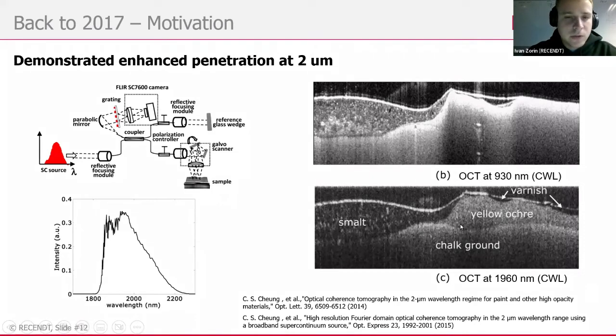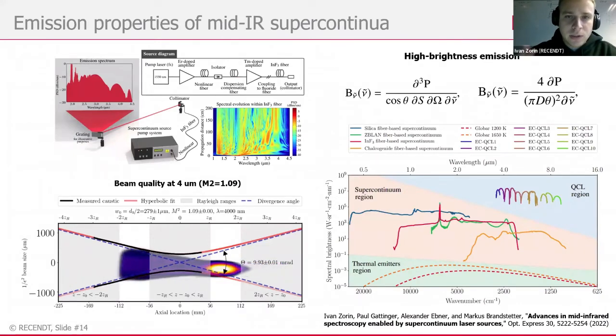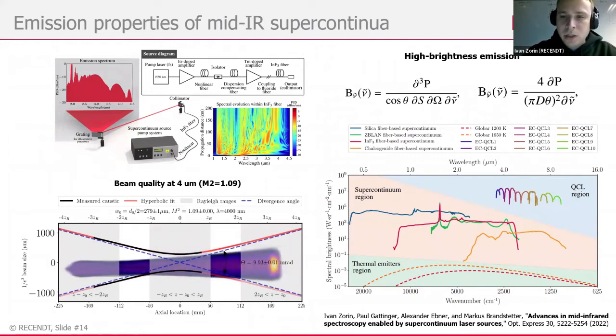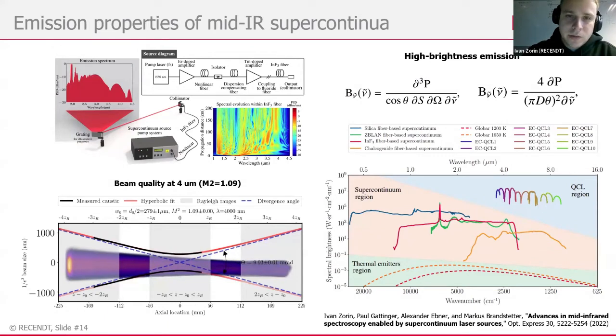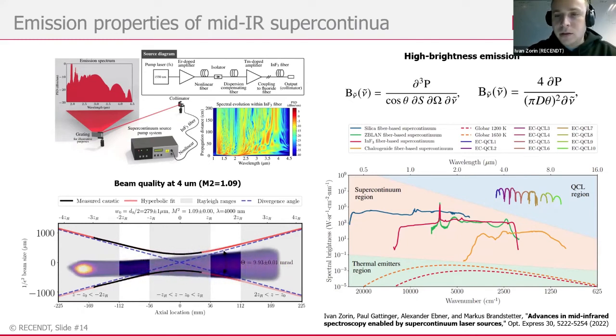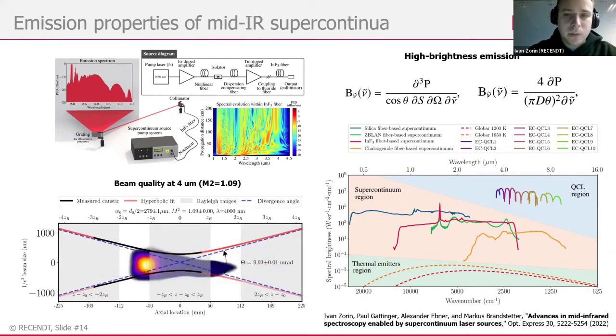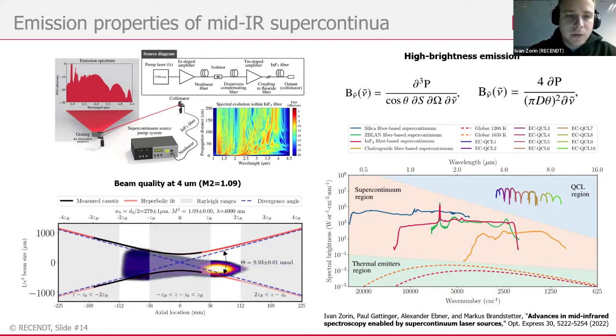Coming to the development of the first mid-infrared OCT system, published in 2018, the first enabling technology was supercontinuum light sources. I won't go very deep into this topic — you can refer to the review paper published this year where sources were characterized and discussed. The sources are very broadband, high power, bright, with excellent beam quality of around M² ≈ 1.1, a little bit noisy, but overall well-fitting for construction of mid-infrared OCT. In our case, the source from NKT Photonics had around 500 mW of average power and around 40 mW in the mid-infrared region of interest.